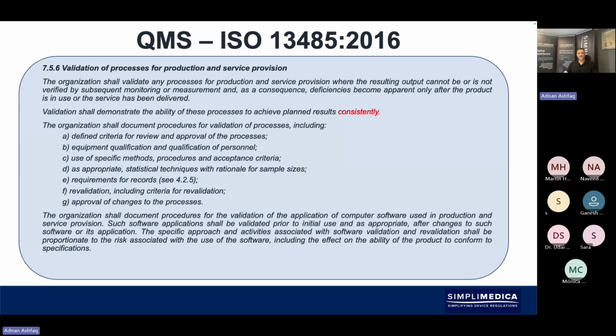Now, this is interesting to note, that it states where it cannot be verified. So the key thing is that there may be a lot of verification taking place within the manufacturing process, and where there's no verification, that's when validation should take place. And verification can be a very costly and very timely exercise. It can be heavily manual, where there's tasks which are being 100% verified, and those would be ultimately replaced by a validated process, which has been quality assured prior to the actual QC inspection taking place. So we'll explore some of those ideas a bit more.